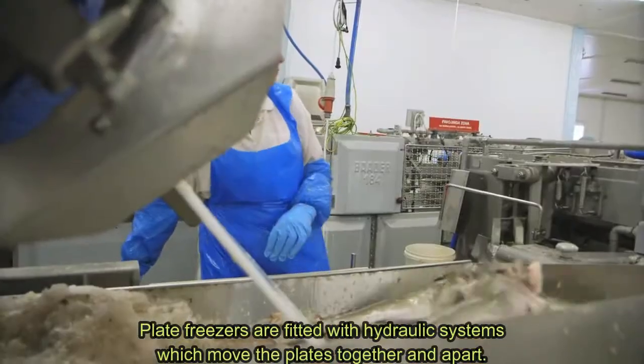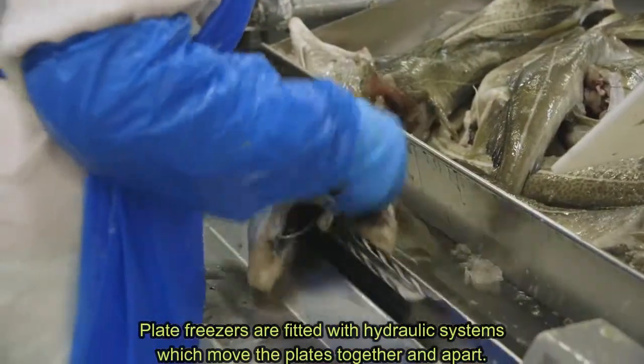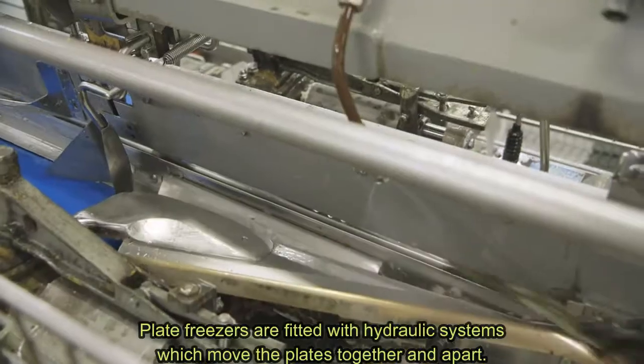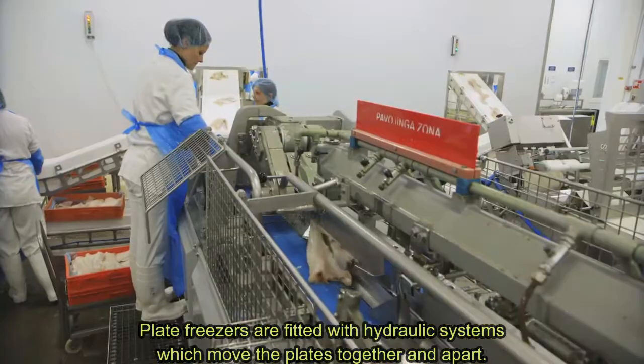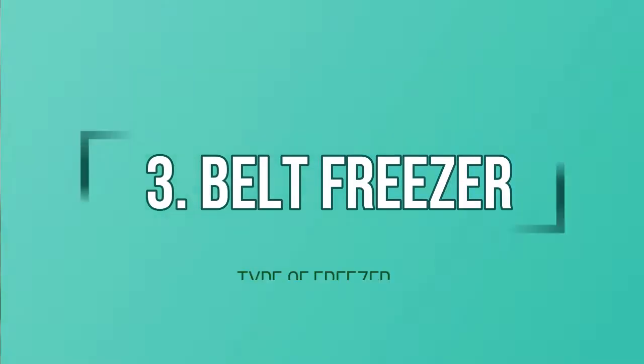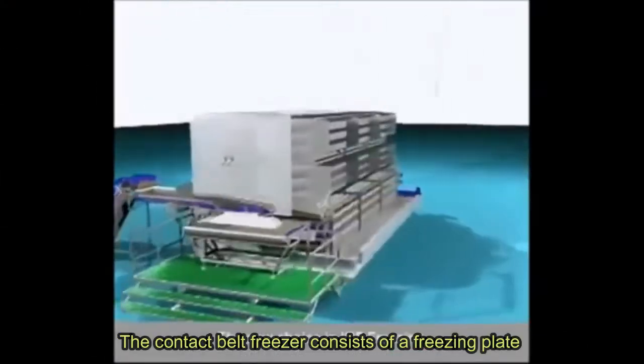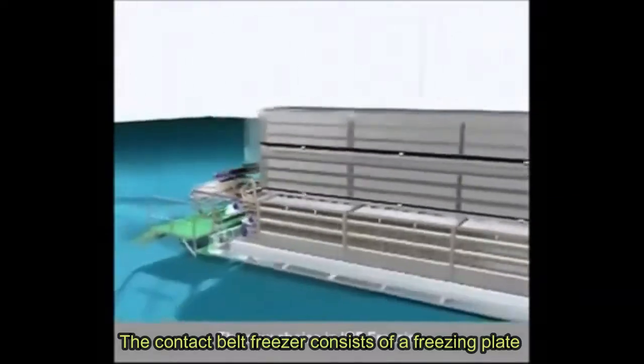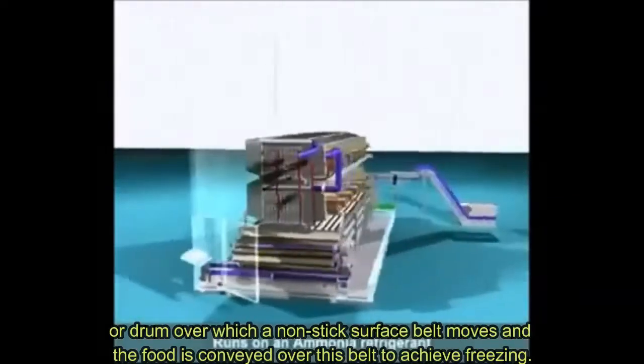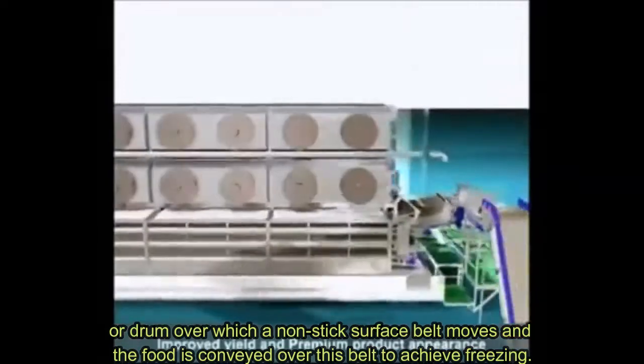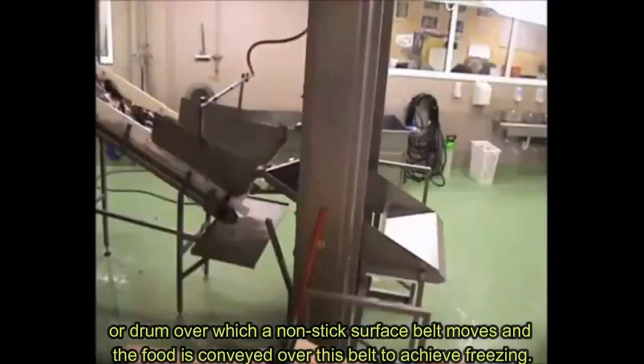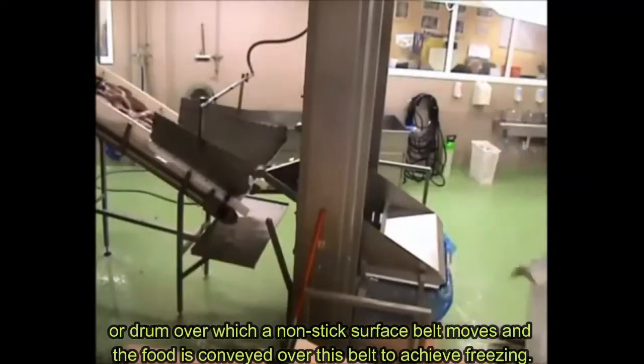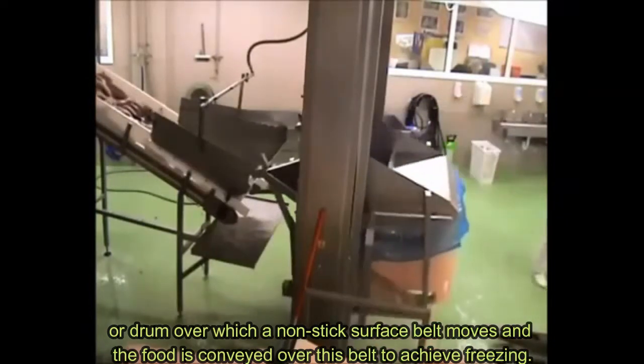Plate freezers are fitted with a hydraulic system which moves the plates together and apart. The contact belt freezer consists of a freezing plate or drum over which a non-stick surface belt moves, and the food is conveyed over this belt to achieve freezing.